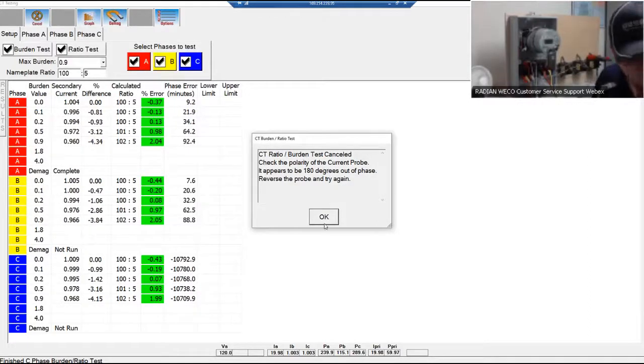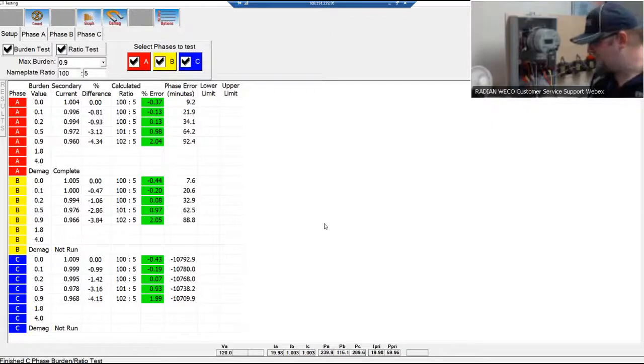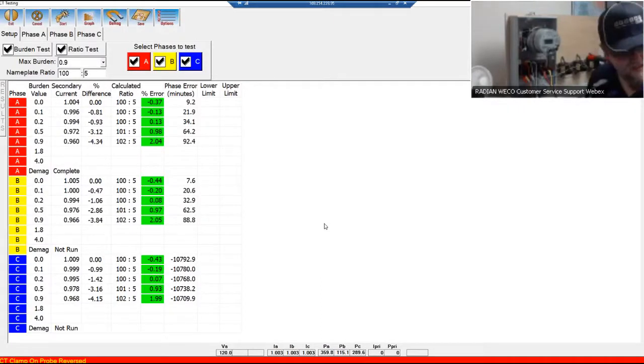So with that being shown off, though, I ran A and B. A and B looks good, but oops, I fat-fingered C, so I want to go back and rerun C. What I can do then is uncheck A and B up here at the Settings tab. And now this time around, we're just going to run C. I take my probe, I purposely threw 180 degrees out, put it in the right direction. You can have this set up either before the test or set it up during the test. It doesn't matter. So if I go ahead and put this back on C like that, it's ready to go. And if I hit start, it'll start the C phase test.